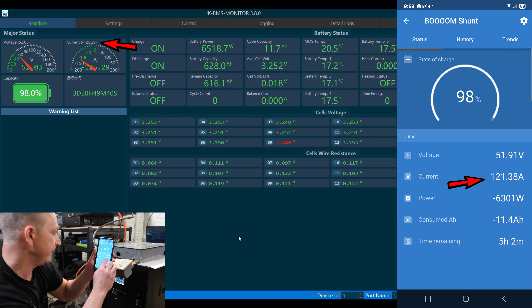So what I'm gonna do next is throw the clamp meter on the positive wire over here to see what that shows. It's showing 127.4 versus what this is showing, 121.4. And the JK is showing almost 125 even, okay? So we're all just a few amps above or a few amps below. You decide on which one's gonna be the most accurate.